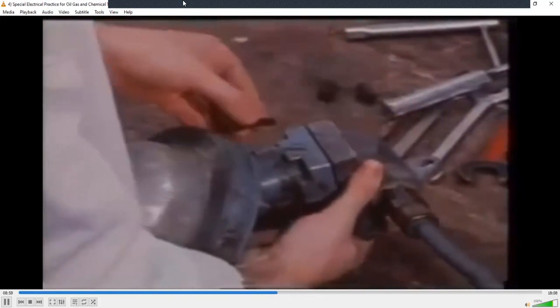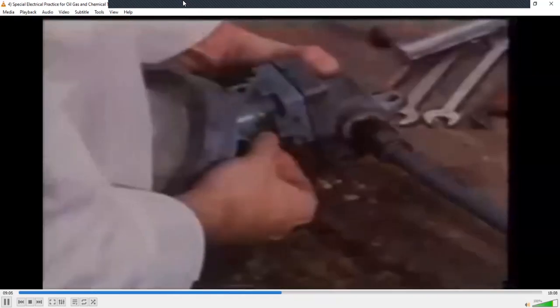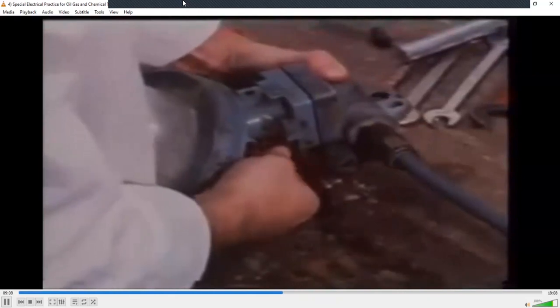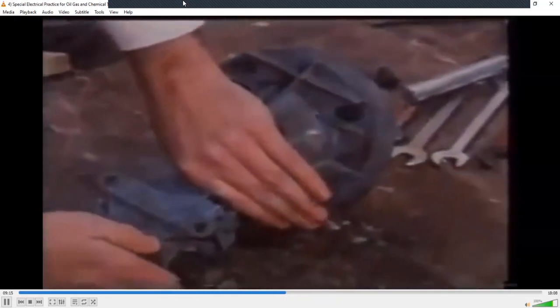When tightening any bolts or nuts holding flanges together, the force used should not be more than necessary to prevent loosening by vibration. Excessive force may cause undetected fracture of a bolt, a casting, or other parts of the securing mechanism.